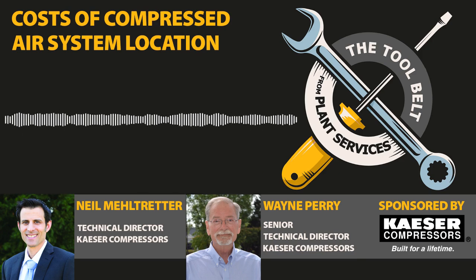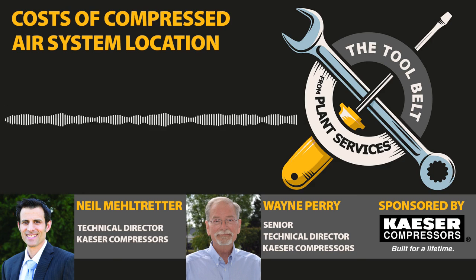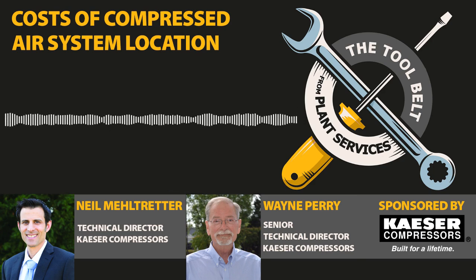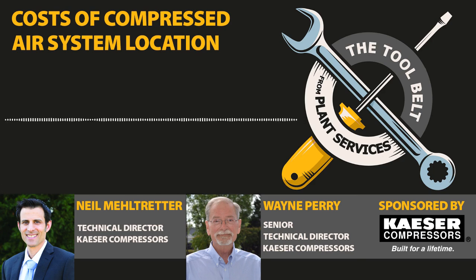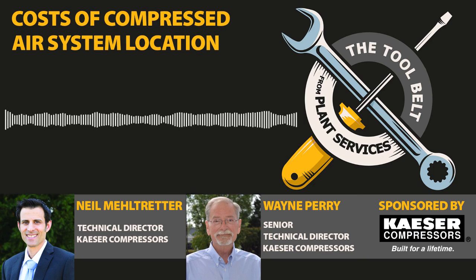You might also consider which are the most critical applications of compressed air, which are the most pressure sensitive, and maybe put the system close to there. What I would recommend against is installing one compressor on one end of the building and another compressor on the other end, because you're never going to get a good pressure signal to be able to control those efficiently. Neil, do you have anything to add?